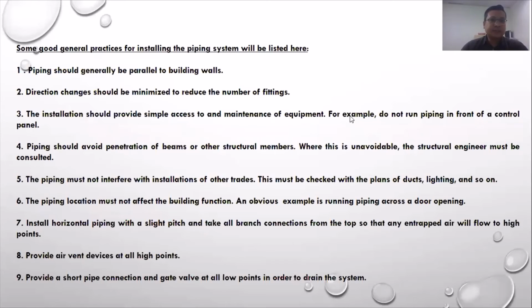Some general practices for installing the piping system will be listed here. Piping should generally be parallel to building walls. Direction changes should be minimized to reduce the number of fittings. So when we design, we try to minimize by using the instrument. The instrument actually is very costly, so we try to calculate the cost. And the installation should provide simple access to and maintenance of equipment, for example, do not run piping in front of a control panel. So when we design the piping system, we include how to maintain it, so we try to make it easy to maintain.